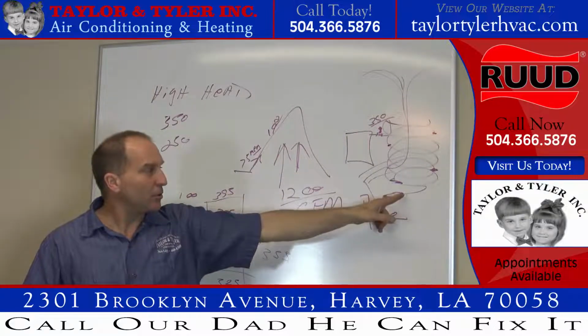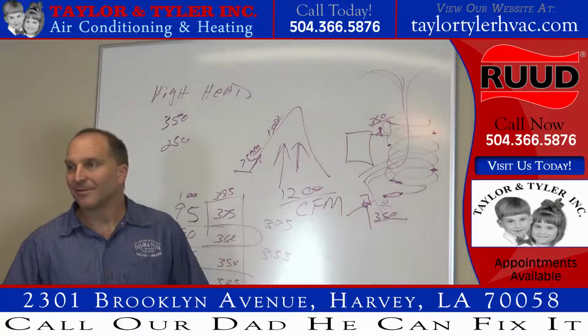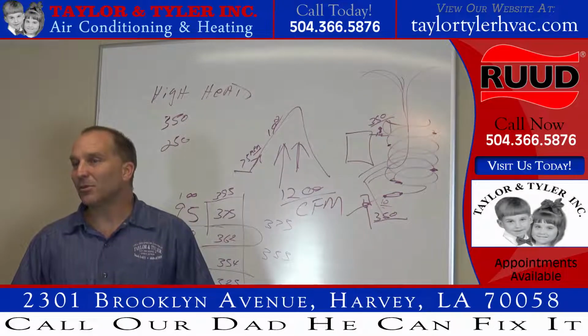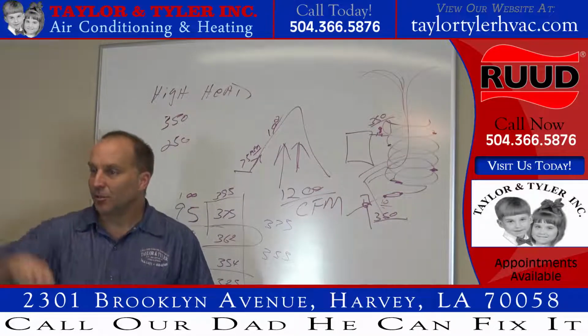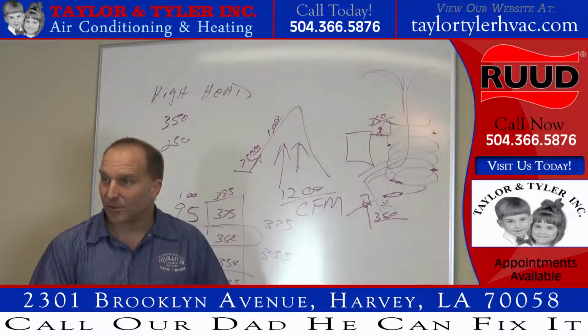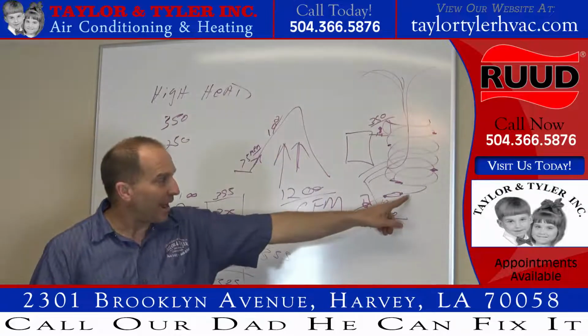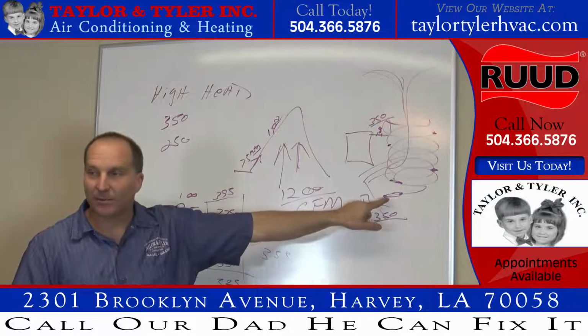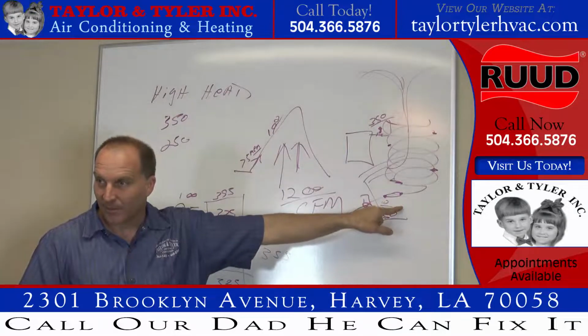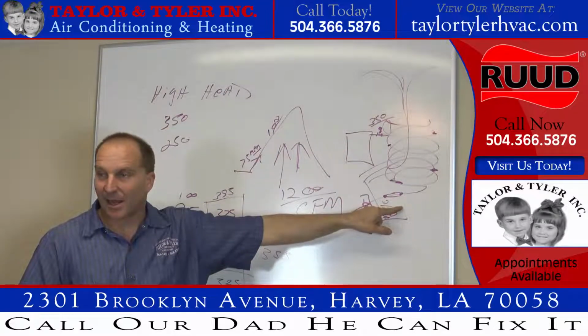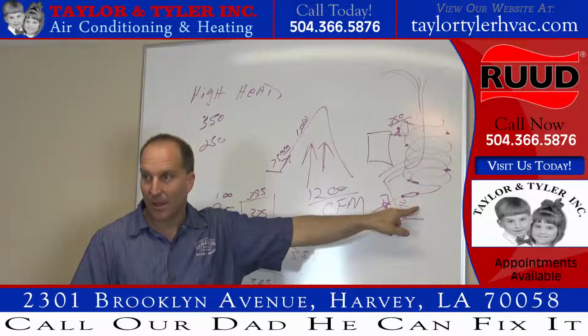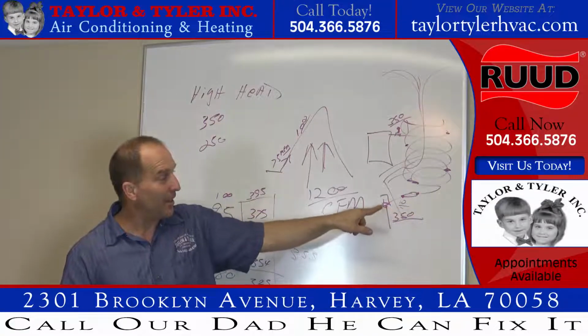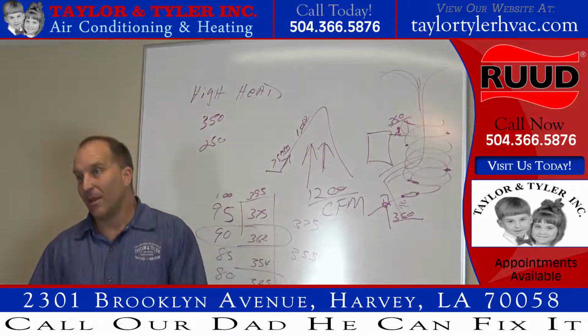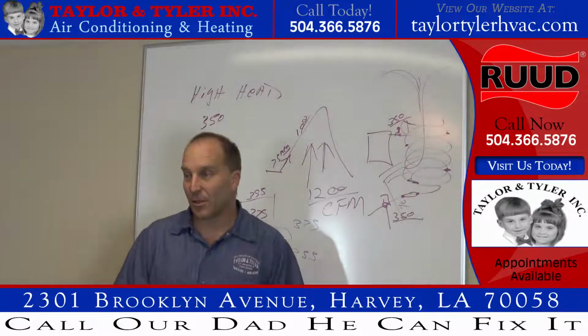You take temperature differentials. Okay. So wherever there's a temperature differential, this will be high, it's going to drop in temperature. So if I've got a higher pressure here than I have here, my restriction's in my dryer. In this particular case, it did not have a bullet dryer in it. My restriction was actually in my service valve. There was trash in my service valve.